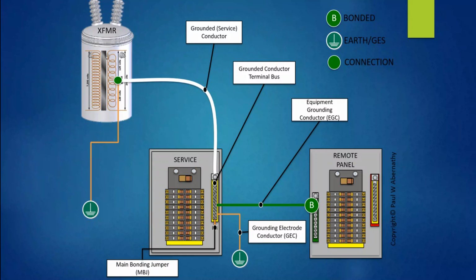Okay. Let's see here. I'm getting all these pop-ups, sorry about that. So here, this equipment grounding conductor, if there's a fault downstream, comes back to this bus, which incidentally goes to the grounded conductor. If there's a fault in this piece of equipment over here, it comes from the equipment through the main bonding jumper over to the actual grounded terminal bus, and allows for the overcurrent protective devices to trip. Now, in this case, this might be a factory installed main bonding jumper, which requires no sizing. If it was a wire, again, you're going to have to size it. We'll talk about that in a second.